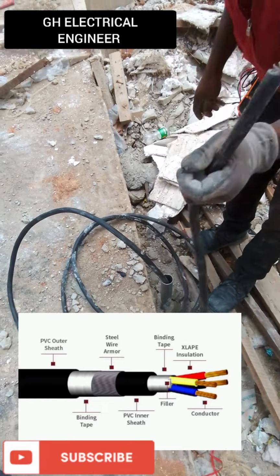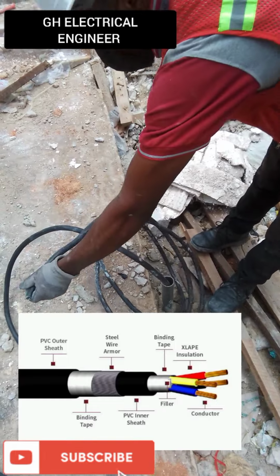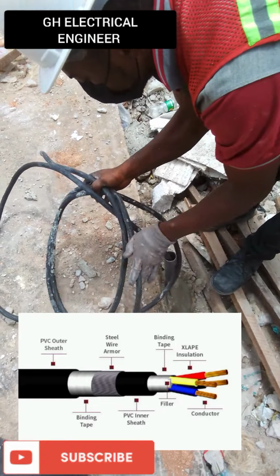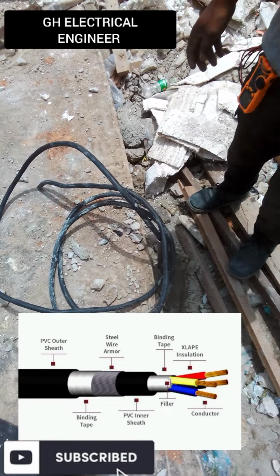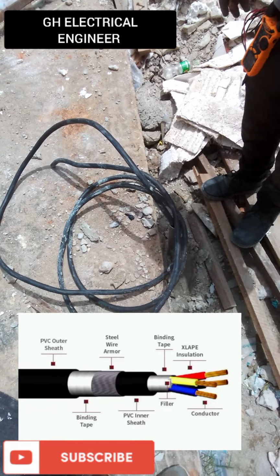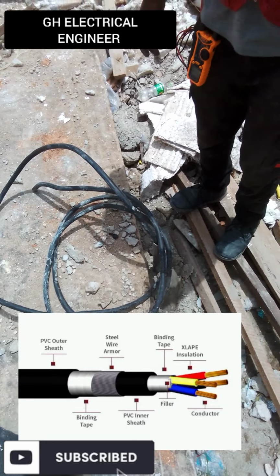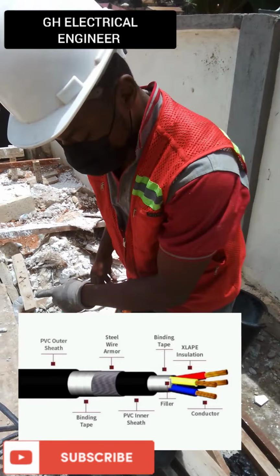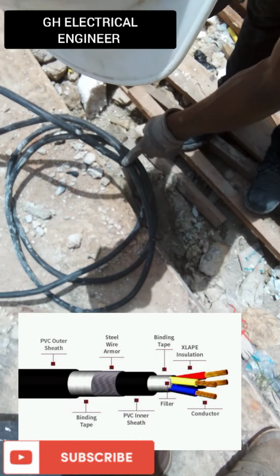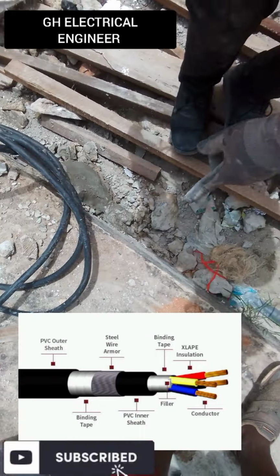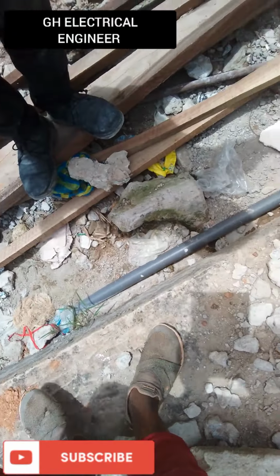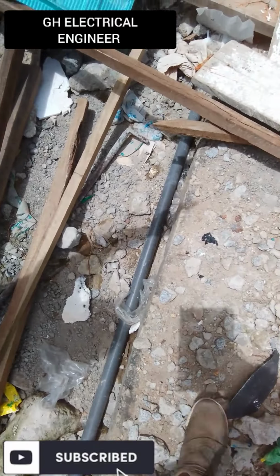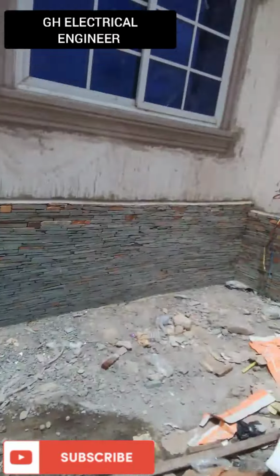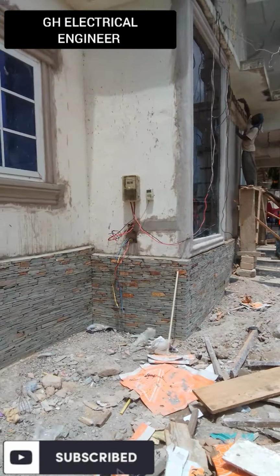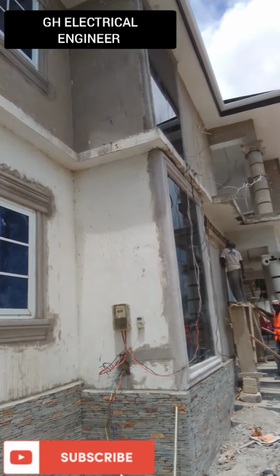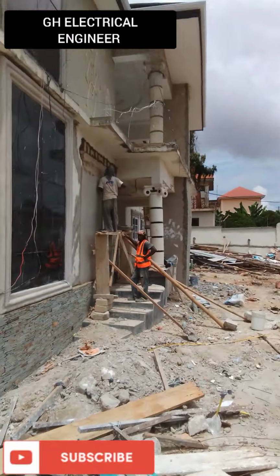A feature that you can see, it has good conductors. It must have a CPC, a sheath. It has to have binding tape. All of them have to be there before you consider that armoured cable a really quality armoured cable. And our armoured cable right here is really quality, but we also bury it with an extra pipe for another extra protection. So it can be here for 200 years without any damage. Most people, because they say it's a ground cable, bury it like that. But we have to be good enough. That is the engineering mindset. We have to make sure we put measures to it.